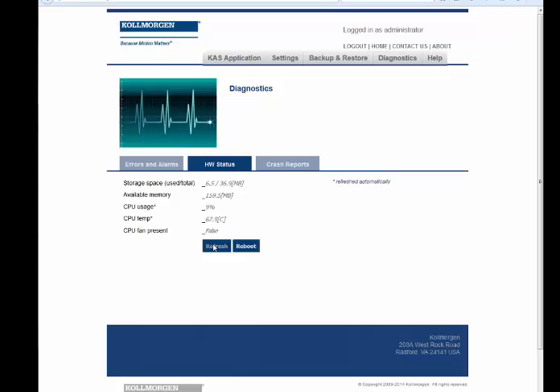If the load goes over 90%, the field turns red. CPU temp displays the temperature of the CPU in Celsius. If the CPU temperature is greater than the CPU warning limit, the temperature background color will be changed to yellow. If the CPU temperature is greater than the CPU's critical temperature, the temperature background color will be changed to red. The normal operating range is 0 to 125 degrees C. CPU fan present is either true or false depending upon if there is a CPU fan in the controller.